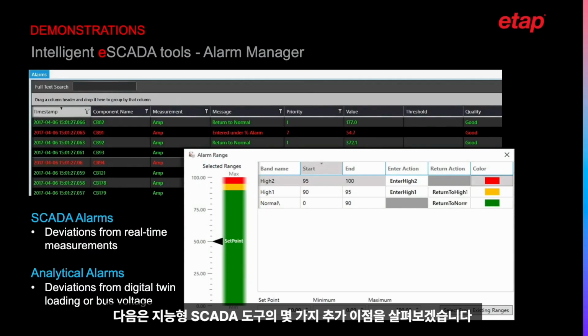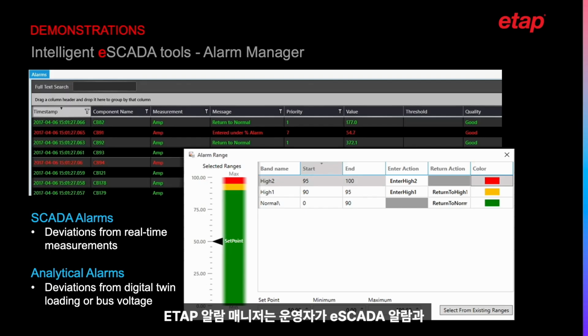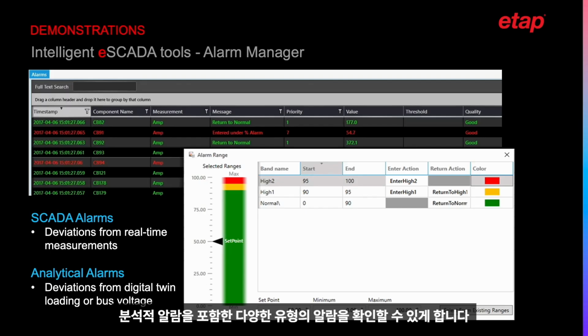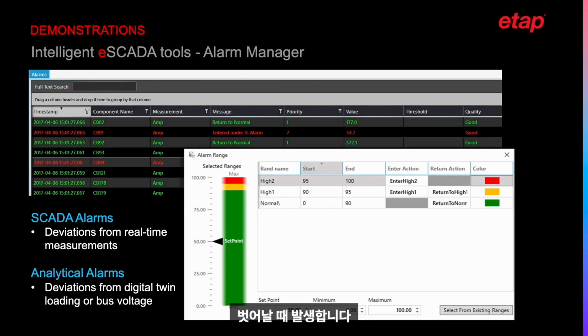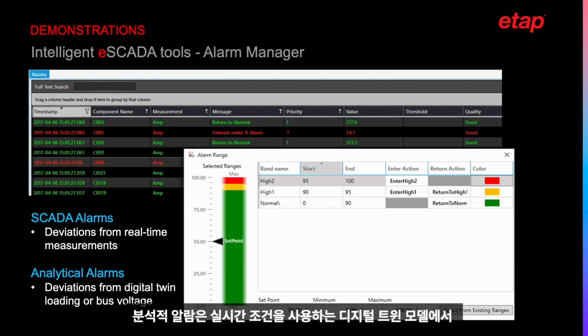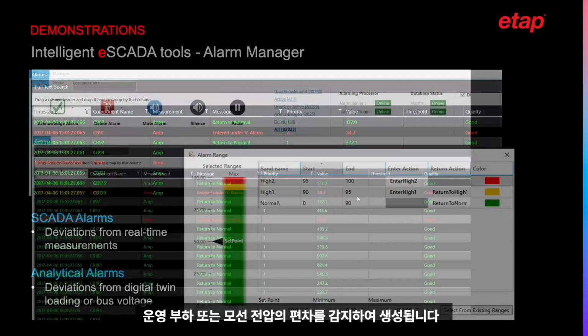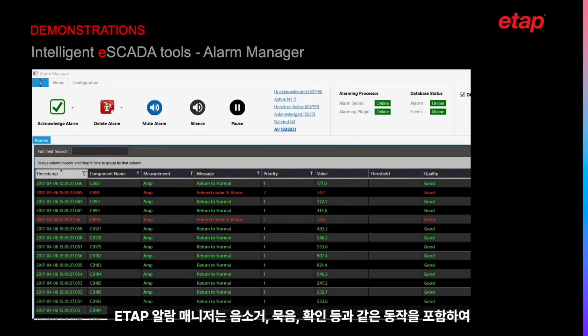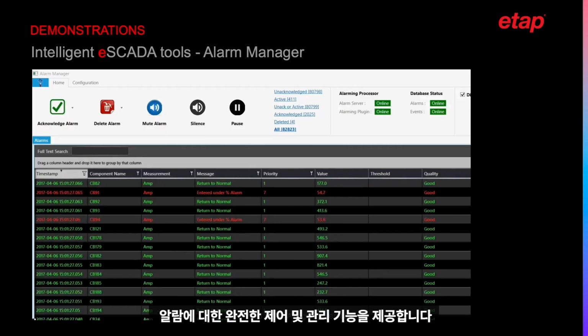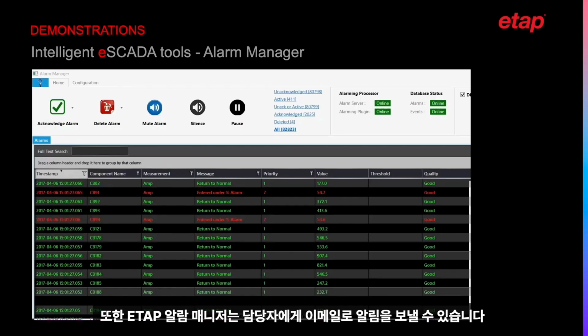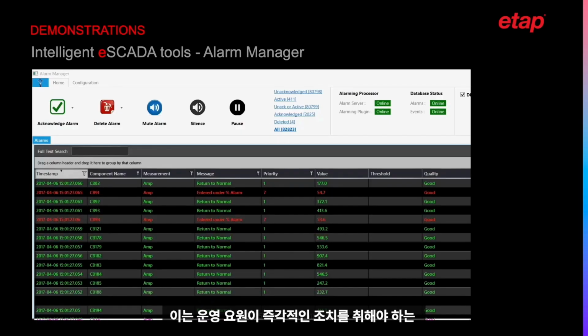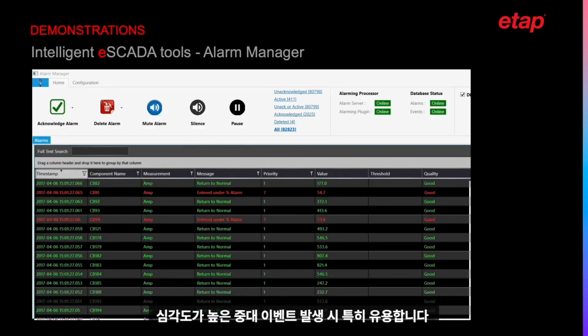Next, we can look at some of the additional benefits of the intelligent SCADA tools. The ETAP Alarm Manager allows the operator to look at different types of alarms, including SCADA alarms and analytical alarms. SCADA alarms are caused by deviations from real-time measurements to an undesired range of operating state. Analytical alarms are generated by ETAP because of detecting deviations in the operating loading or bus voltage in the digital twin model using real-time conditions. The ETAP Alarm Manager provides full control and management of alarms, including actions such as mute, silence, acknowledge, and more. In addition, the ETAP Alarm Manager can send notifications via email to personnel. This is particularly useful for critical events with high severity that require operations personnel to take immediate actions.